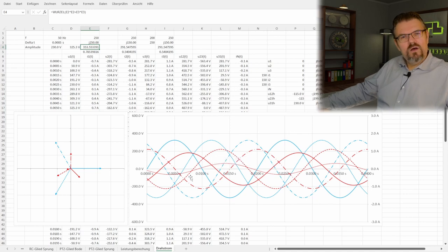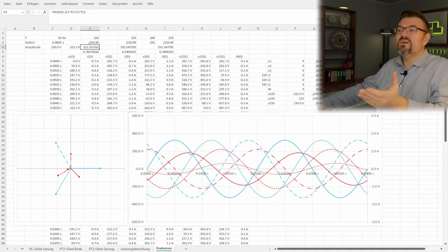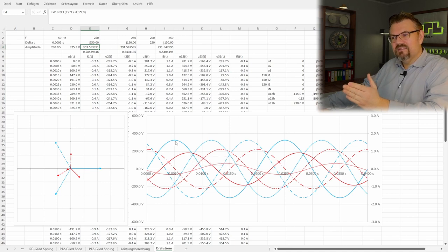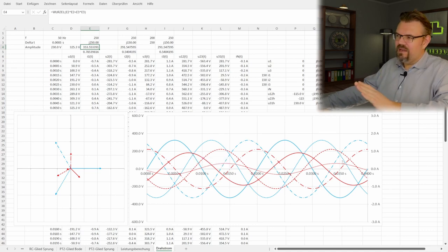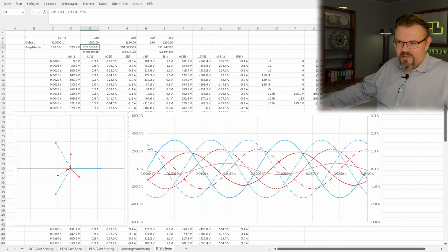And now, the sum of all three, because one is getting smaller and it's also getting a little bit delayed. The phase is now a little bit later. The three are not level anymore. And this is why we have this thin red sine wave now. This is the neutral current. In the pointer diagram, if I had this and this and this, I would end up here. Here we see the neutral current is a small pointer, almost 180 degrees behind U1, and this is also true because when this is going down, this is going up, so we're almost 180 degrees behind.